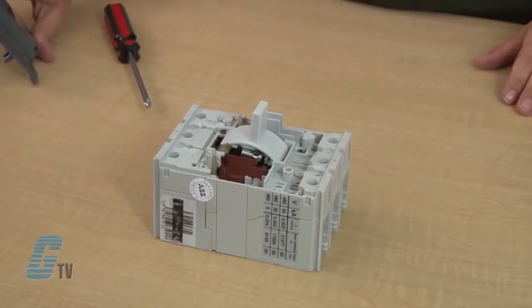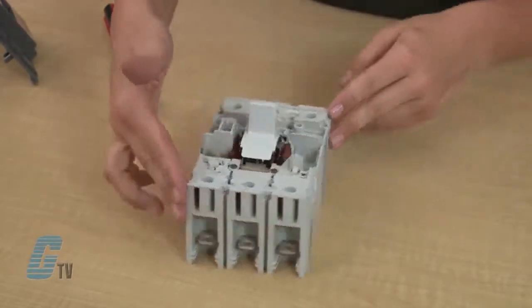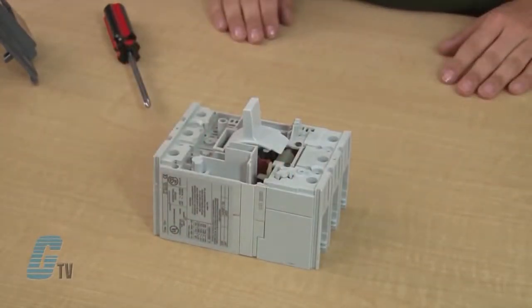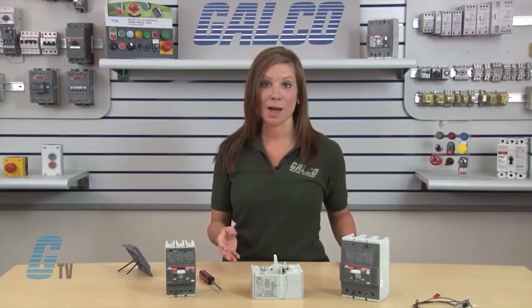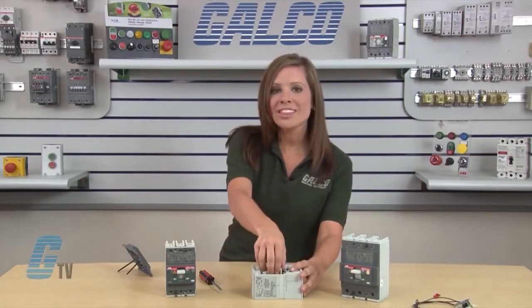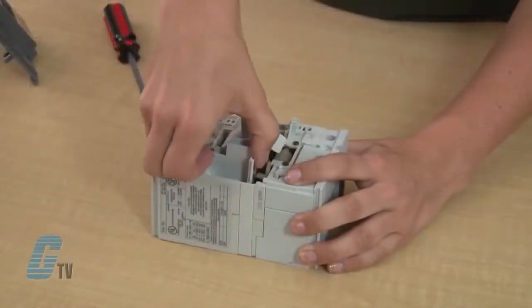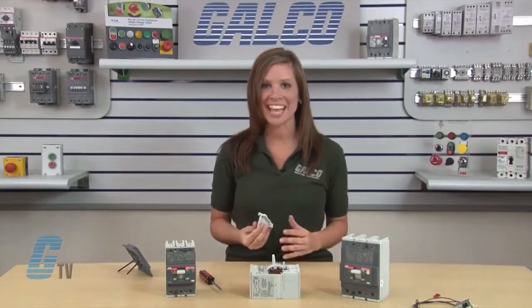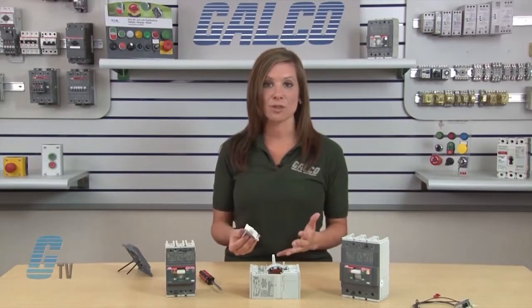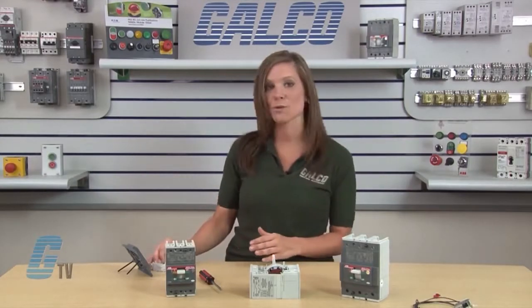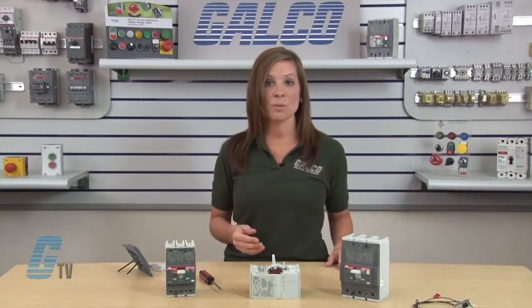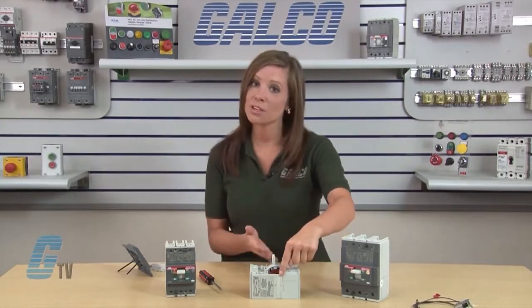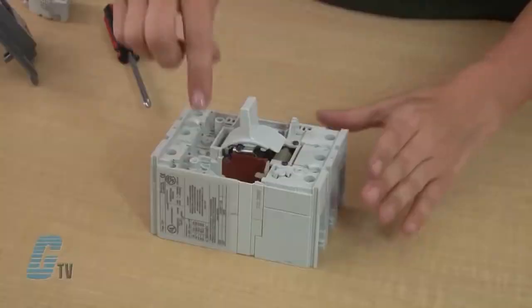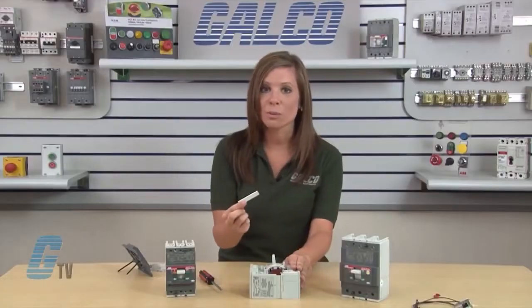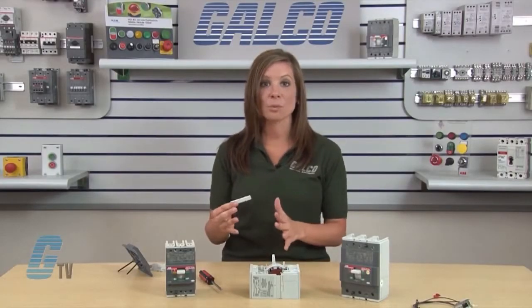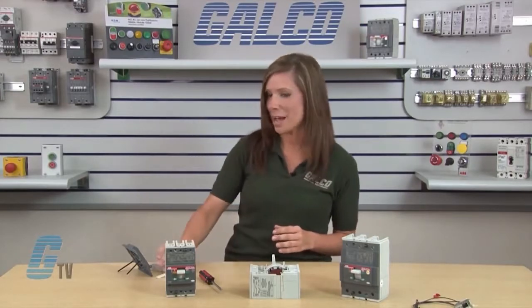As you can see, the T2 model has a protective cover where this accessory will go. This cover is not present on the T1 or T3 models. To remove the cover, I will pull on the top of the protective cover outward and downward until it is free from the frame. This cover will not be used after the UVR is installed, so I will set it aside for recycling. Next, I will remove this side cover where the wires will be routed. It is easily done by sliding it in the grooves toward the front of the breaker until it is released. I will reinstall this in a moment, so I will set it aside for now.